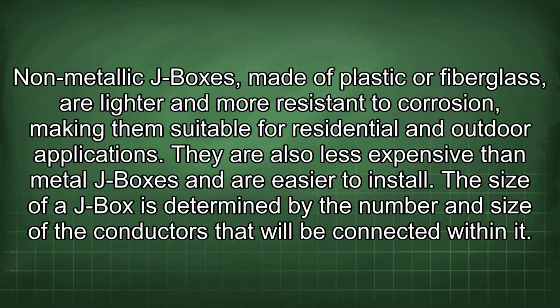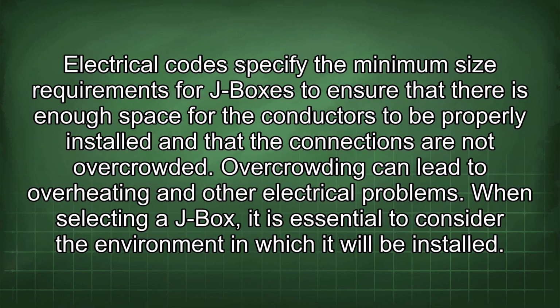The size of a J-box is determined by the number and size of the conductors that will be connected within it. The electrical codes specify the minimum size requirements for J-boxes to ensure that there is enough space for the conductors to be properly installed and that the connections are not overcrowded. Overcrowding can lead to overheating and other electrical problems.